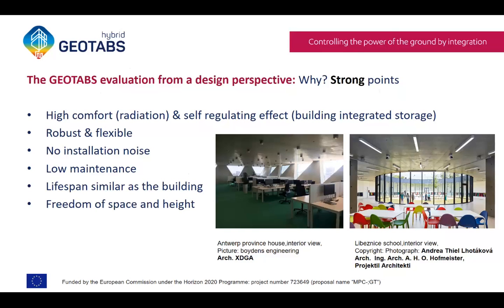On top of that, because of the concrete slab, there's a lot of heat or cold stored in it, so it can cope with an excess load for quite a long time - we're talking about days here. The comfort is very robust. Even if you have a power-down situation, if your heat pump has a problem and shuts off, you won't feel it in the comfort for a day or more.